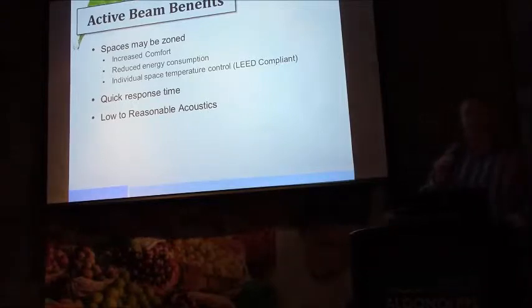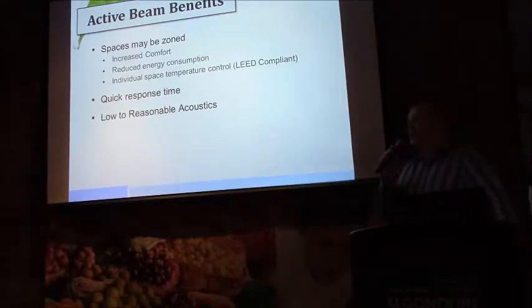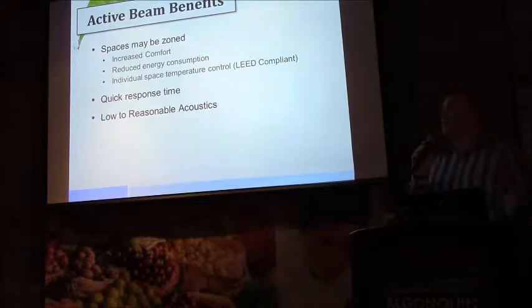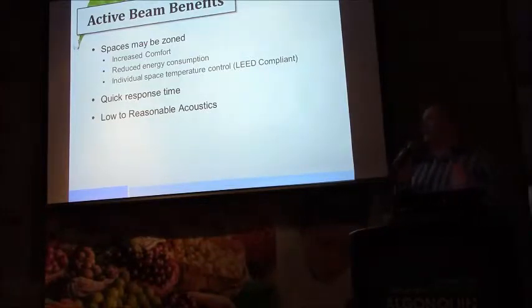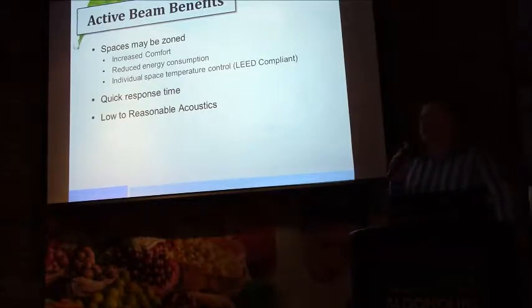And that also becomes a talking point in terms of the selection. Again, the beams are a sheet metal box with coil in it. If we have an application and we have a deliverable by the client whereby that space needs to be quiet, and these spaces are adding logarithmically to the acoustic content of the room, it's important to understand where that spectrum is an issue and address it.